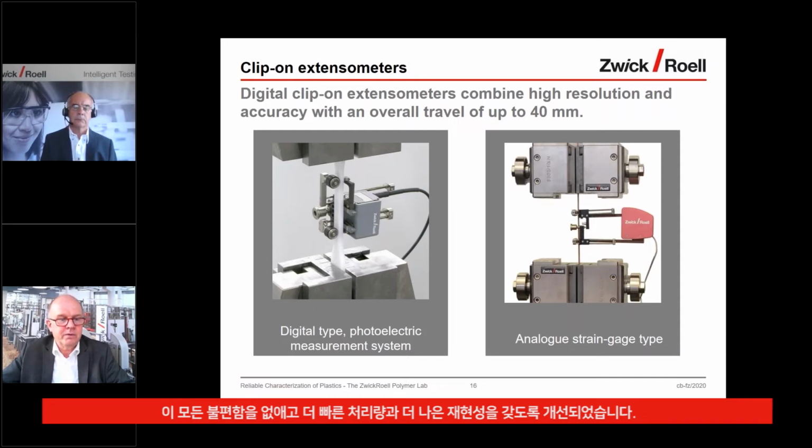Right. So, Helmut, we've mentioned temperature chambers now, and I think this is another interesting topic to move towards, perhaps to discuss a little bit more. The process of mechanical testing inside a temperature chamber hasn't really changed that much for many years, I think. These technically quite simple heated or cooled cabinets are often difficult to set up. They have different control systems, control electronics and buttons to push and so on. They can be quite time consuming to operate.